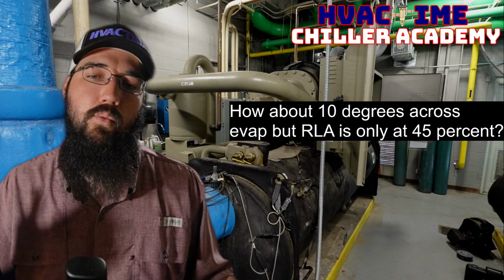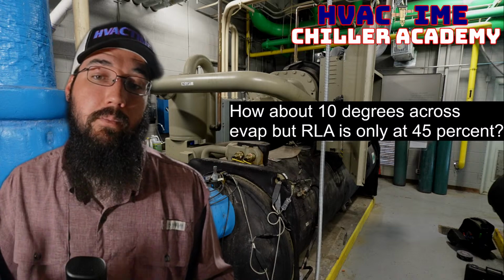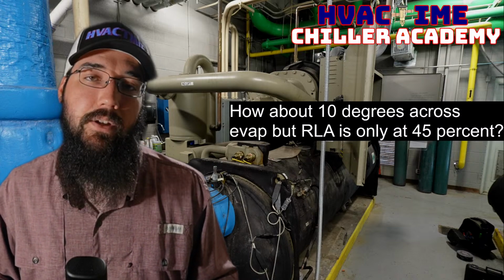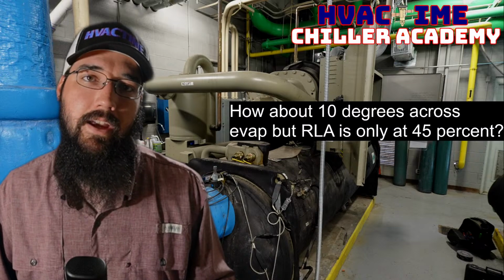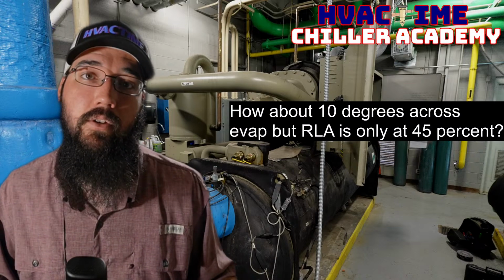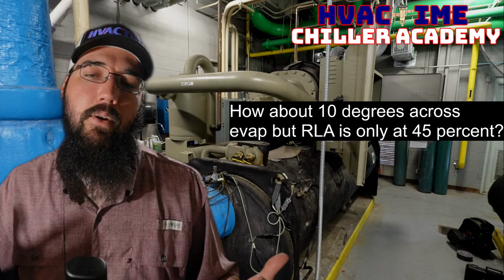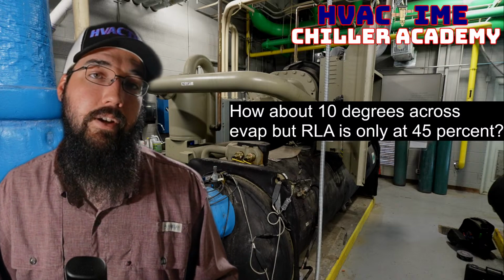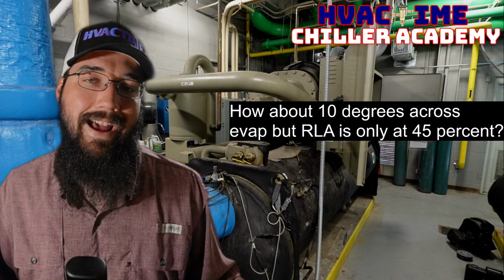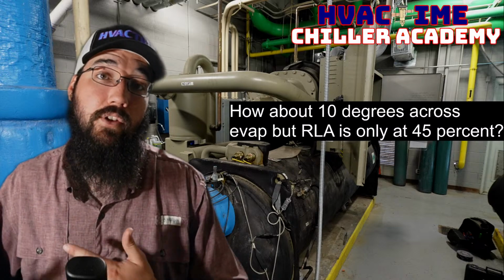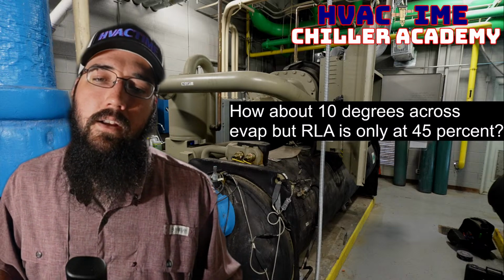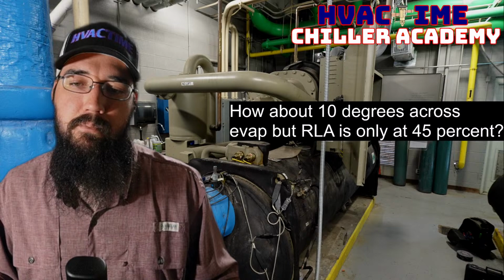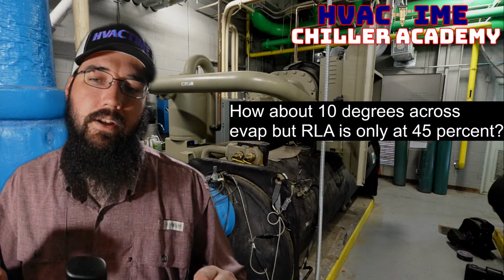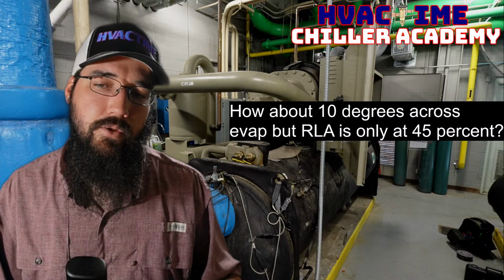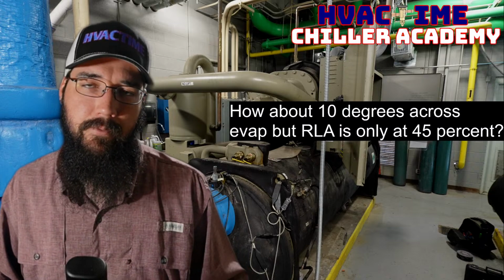And we may not have a lot of load, but we'll be able to make 10 degrees really easy, because that water has so much contact time because it's flowing so slowly through the evaporator that we're able to make 10 degrees even though we don't actually have a lot of BTUs flowing through the chiller. Now, another thing I want to address here is you've got 10 degrees, but only 45%.